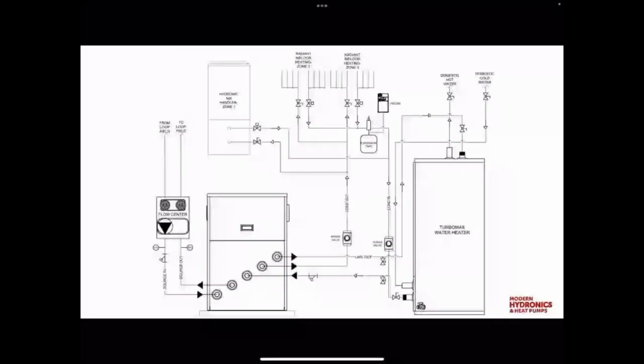I did want to show real quick here, this is just kind of a standard piping diagram. On here we can see that there's a couple radiant zones, there's a hydronic air handler right here. This is just showing the common port layout. This would be for the electric backup. But this would be the direct to load piping concept, which is in the IOM manual for the current Rev A WV that we have on our websites. There will be a new IOM manual coming soon for this new version. But these piping diagrams will still be relevant because the same strategies will be employed with this new unit.